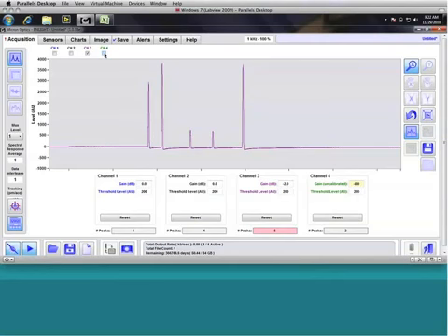Okay, we can see in the purple diagram that we have 5 spectral peaks, or we have 5 features that resemble peaks. But when we look down underneath the channel 3 acquisition controls, we see that there's a number of 5 peaks, but that it's got a light red background. So this indicates that the number of peaks that the SM130 had been detecting and expects to detect has changed. And that makes sense because we've now inserted this fiber and connected the fiber to the interrogator.